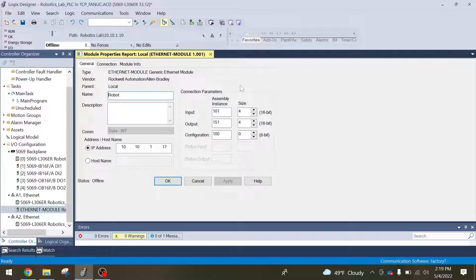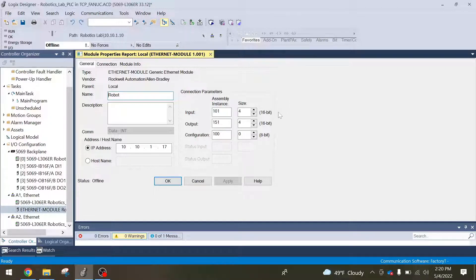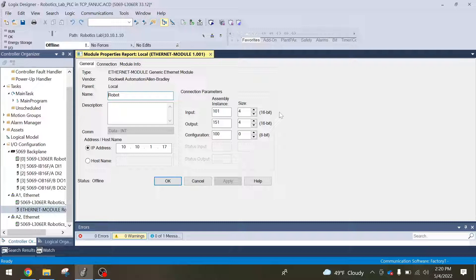Then you're going to set up your assembly instances. This I'll get more into in the section where we map our digital and UOP IO in the Ethernet IP config menu on the robot. But your size correlates directly to when you did your configuration of the adapter. In there we set that we wanted to transfer four 16-bit words back and forth from the robot. So in this we're going to do the same exact thing. It's going to default to I think about 125 and 124. You want to change these to four because it will not connect if the PLC thinks it's sending more information than the robot's actually sending. These are all also available on the Ethernet IP manual from FANUC. It'll show you these as the generic setup and that's what I'm using because it functions pretty well.